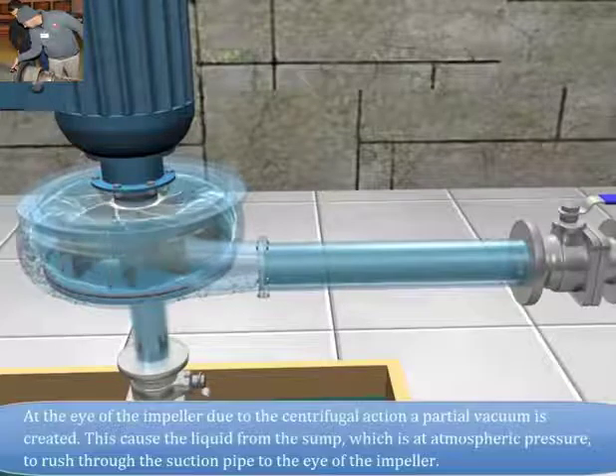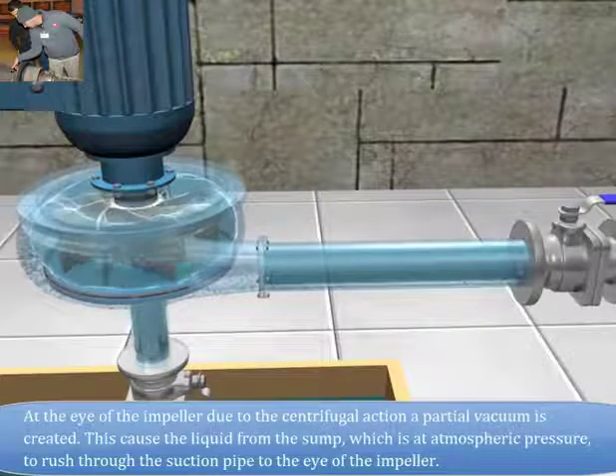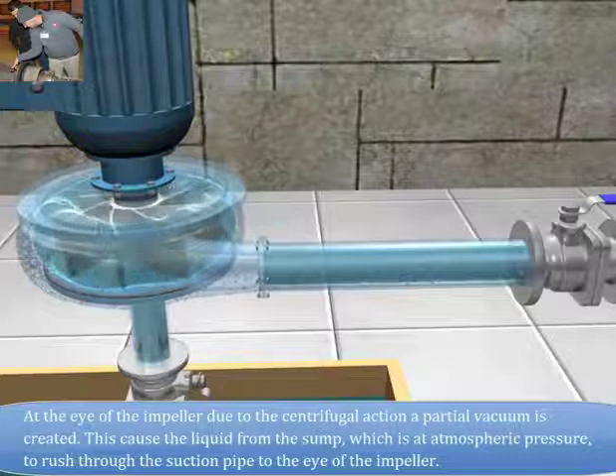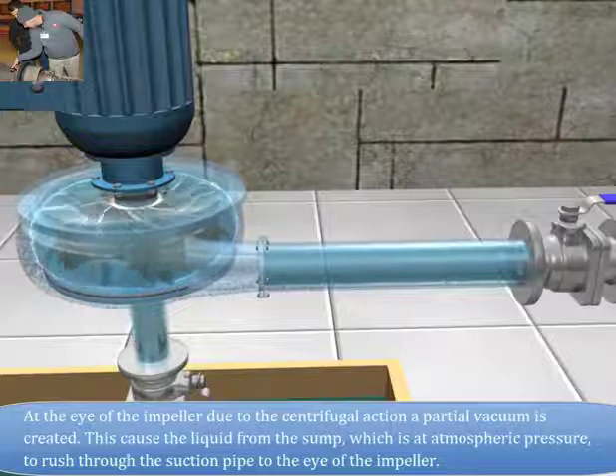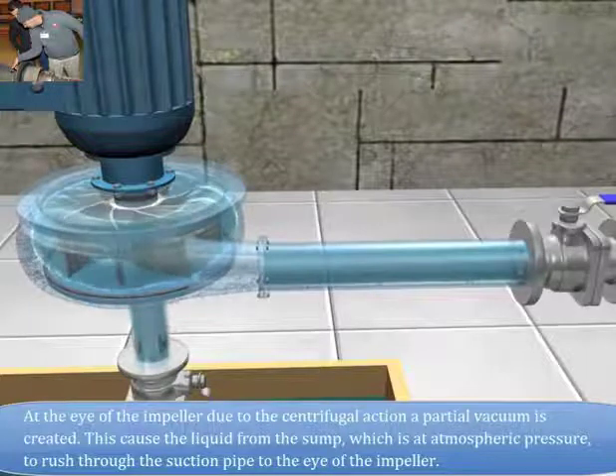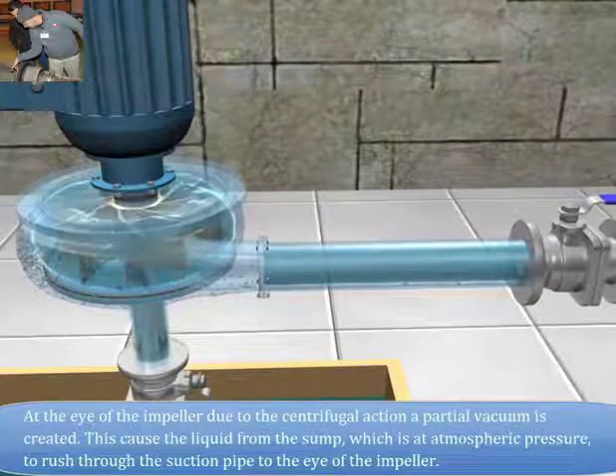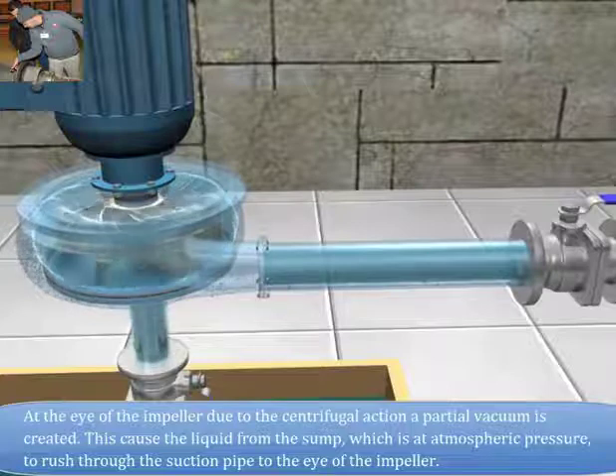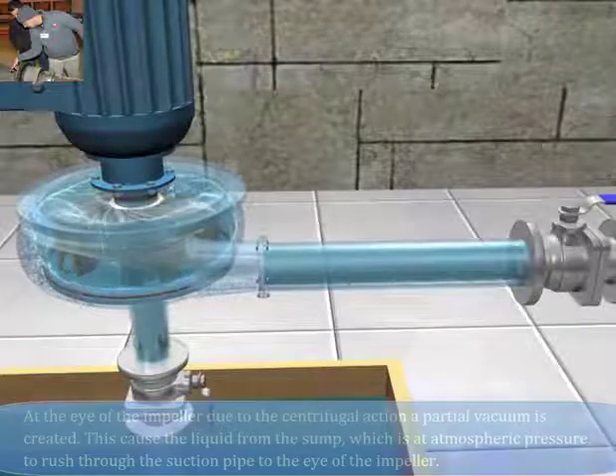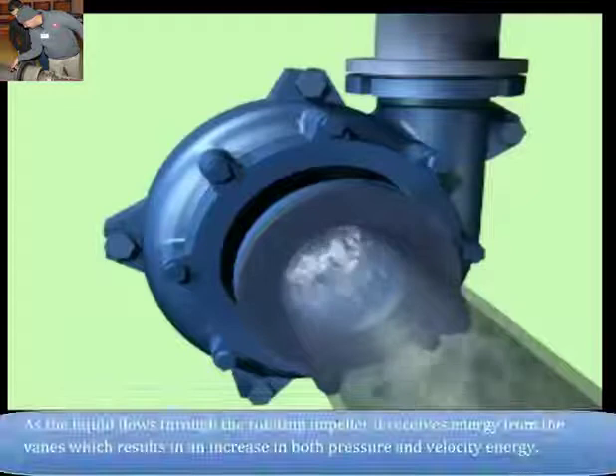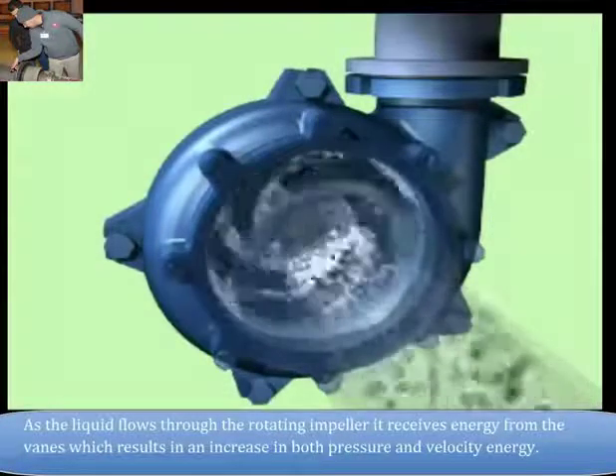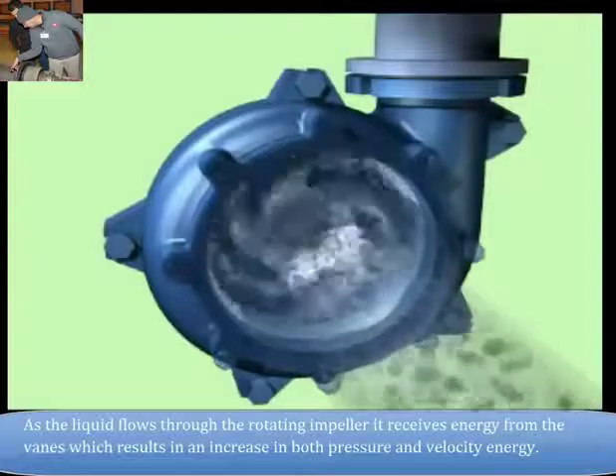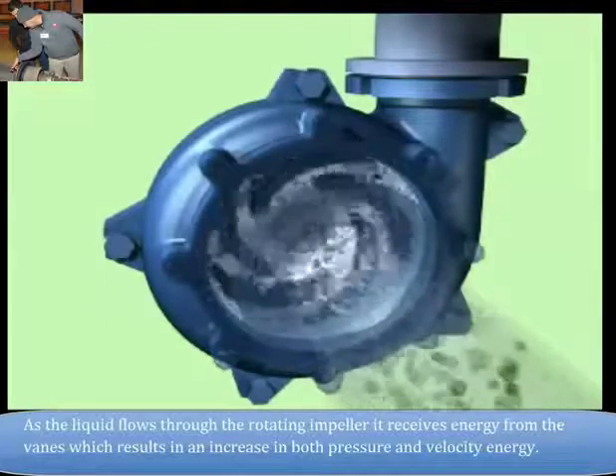At the eye of the impeller, due to the centrifugal action, a partial vacuum is created. This causes the liquid from the sump, which is at atmospheric pressure, to rush through the suction pipe to the eye of the impeller. As the liquid flows through the rotating impeller, it receives energy from the vanes which results in an increase in both pressure and velocity energy.